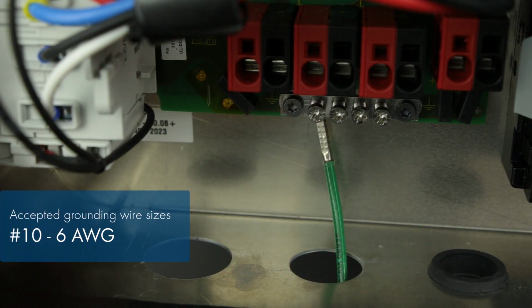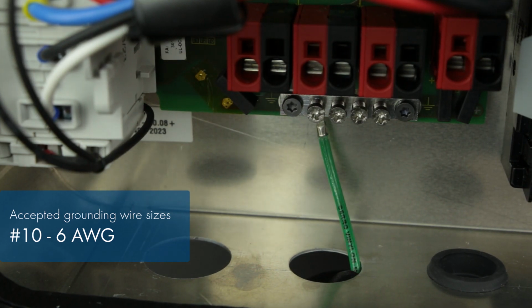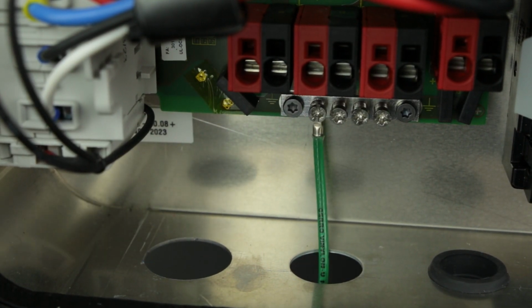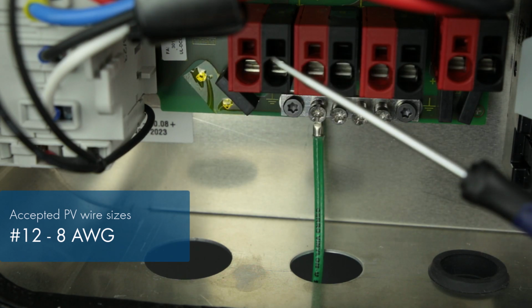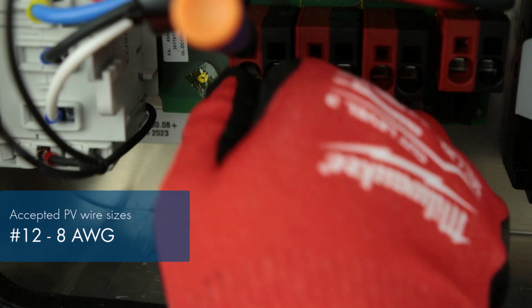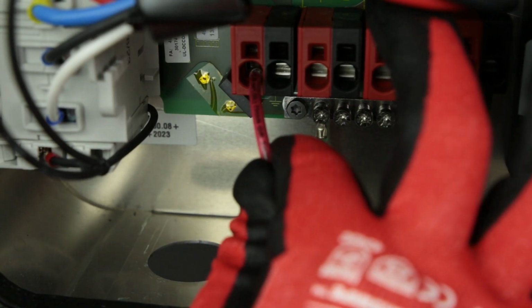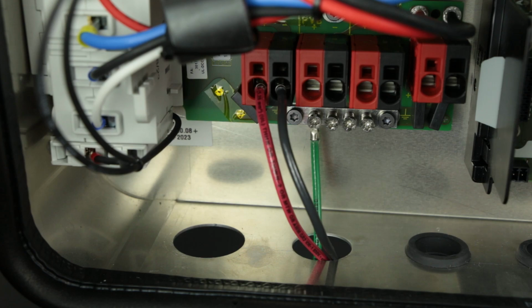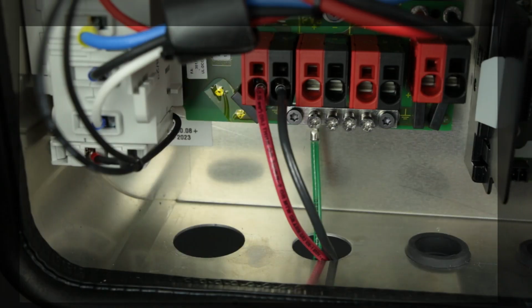For the DC wiring, start by grounding the equipment ground conductor to the bus bar and secure it with a screwdriver. To install the PV positive wire, first insert a screwdriver here to open the clamp. Then, insert the wire into the terminal hole. Do the same steps for your PV negative wire. If applicable, repeat these steps for your remaining PV conductors. And be sure to seal any unused knockouts with sealing plugs.